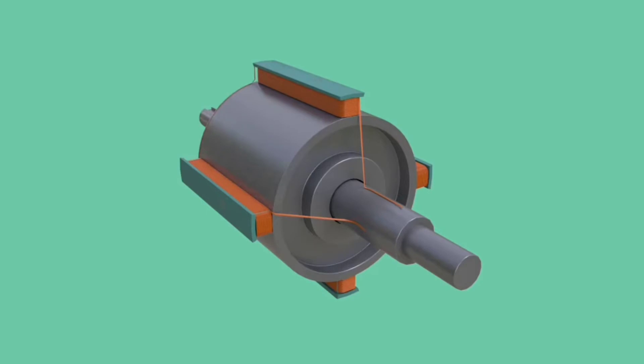DC current is supplied to rotor via a pair of slip rings. This is the reason why rotating magnetic field approach is used in alternator. If rotating coil method were used, slip rings have to fit along with the armature coils in order to collect electricity, but transferring such high-voltage electricity via slip ring is rather impractical. It is quite possible to transfer low-voltage DC excitation current via slip rings.